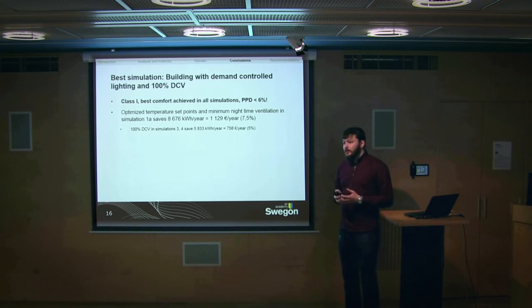Additionally, including 100% demand-controlled ventilation saves almost 6,000 kilowatt hours per year. When I was investigating the building management system, I saw that there was a lot of constant ventilation, even though the demand-controlled ventilation equipment has been installed. For some reason, the set points had not been set in such a way that demand-controlled ventilation could be achieved. But by doing that now, you can save about 750 euros per year in operating cost.